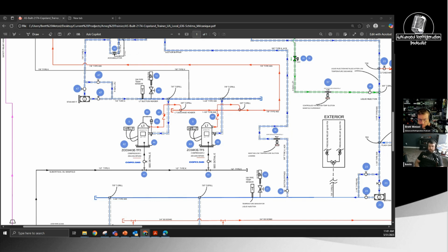Like for me, it was nice. We learned a little bit about it because I didn't know on those SH1 controllers, when you go to do superheat on CO2, you have to use 4 to 20 milliamp transducers. Even though they have a 0 to 650 in there for ratiometric, you can't use a ratiometric transducer on CO2.